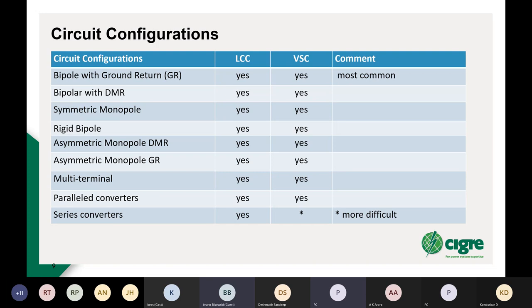Asymmetric monopole with a DMR, that's not a very common configuration because it requires that you have a full voltage cable or line on one side, whereas with the symmetric monopole you have basically half the voltage on each cable or line conductor. Asymmetric monopole with ground return, again, is a similar configuration to the configuration with the dedicated metallic return.